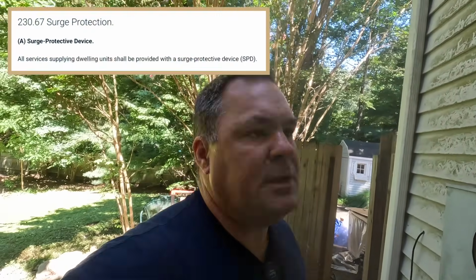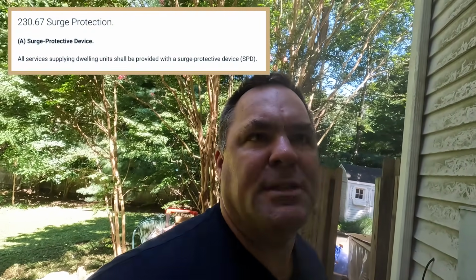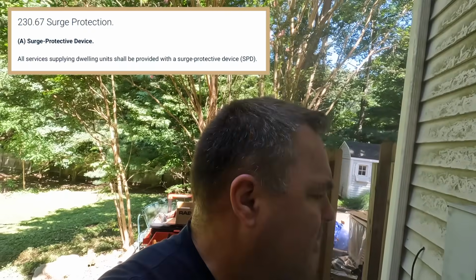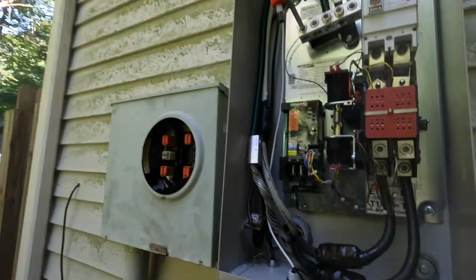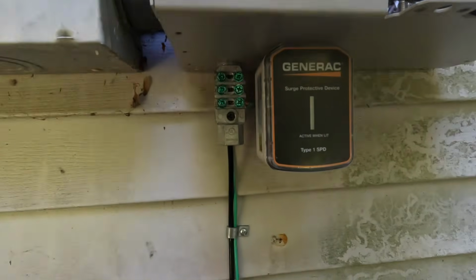So this is definitely something I haven't been asked to do before, but since the 2020 code has been the electrical code in New Jersey, you have to put the surge protection in for services. If you read that section closely, I believe it's 230.67. It could be 230.85, I forget which one. One of them's for the disconnects, one of them's for the surge protection requirement. So we're updating the service equipment here because this transfer switch is now the main disconnect. All right, so the inspector here is asking me to put in a surge protective device, which I'm doing.